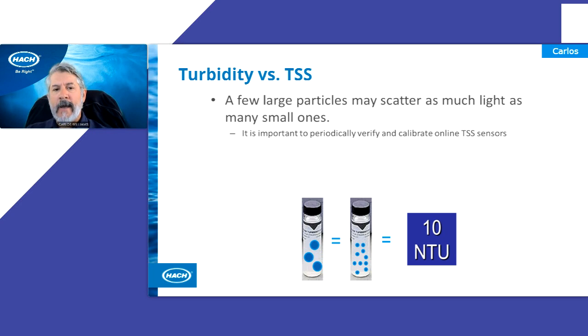So just one word about this: you guys are going to hear my colleagues talk a lot more about correlating solids and turbidity, but this is an important thing to remember. What I have here are two sample cells, one that has a few very large particles and another sample cell that has a lot of small particles. Something measured by turbidity will scatter the same amount of light, and so it will give you the same turbidity value. However, if you're trying to get a suspended solids value, those two might be completely different. The point being, if you think your sample stream is going to be highly variable, or there are going to be times of the year or times in a certain process where you see differences in the suspended solids measurement or in the turbidity measurement, it's always good to at least verify, if not calibrate, your turbidity device that you're using to measure suspended solids.